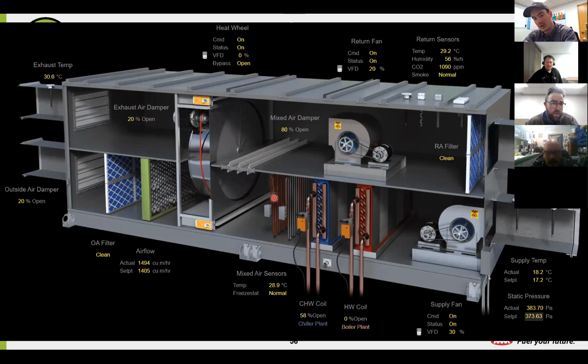So anyways, this is an interaction between all the different things we've talked about so far. We talked a little bit about ventilation, especially with COVID. We need a certain amount of inside air exchanges, so we have to bring in outside air. We need to consider the building pressure. We want a slightly positive building envelope. That way all the air coming into the space is controlled. So we're pulling it in from outside, and the building isn't going into a negative where you can't push the doors open. But we don't want the building under so much positive pressure that the doors are blown wide open, not closing, things like that.